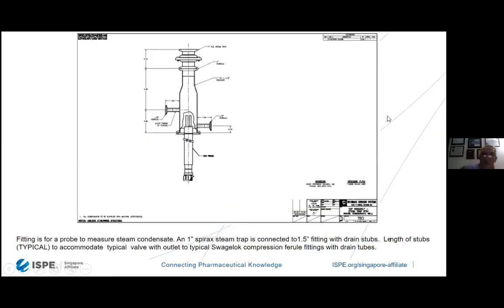You can also use Rouge in a steam system. This is showing a pure steam system at the top, which is a little more difficult to see across here, would be the steam header, and there would be a small 1 inch line coming off of that, of which we have a Spirax Sarco steam trap, which will be used as a condensate trap, which will convert it over into water from steam.